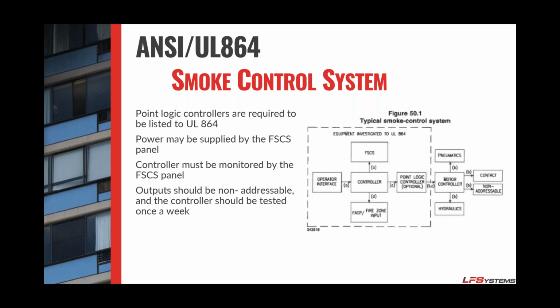And the fight will be, well, no, we're just a motor control. That is what most drive manufacturers will tell you: we're just the VFD, we don't have to be listed. But as soon as you put a sensor to it, and a lot of guys use the term smart drive, that smart function basically bounces it back over to here. So while the sensor doesn't necessarily require that listing, that control will.